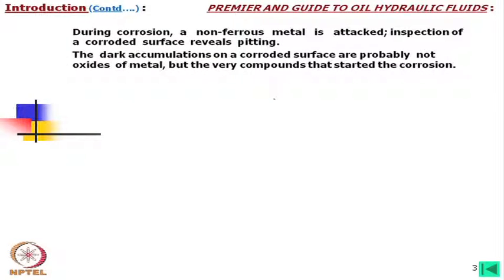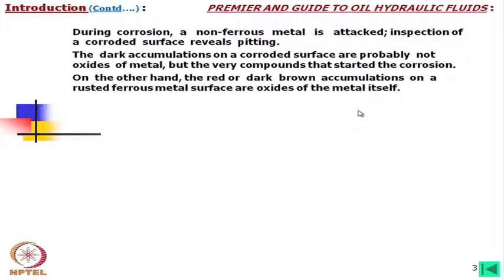The dark accumulation on a corroded surface is probably not oxidized metal but the very compounds that started the corrosion. On the pitted or corroded surface you may find some dark debris — we might think it is oxides of metals, but it is normally those compounds. On the other hand, the red or dark brown accumulations on a rusted ferrous metal surface are oxides of the metal itself.